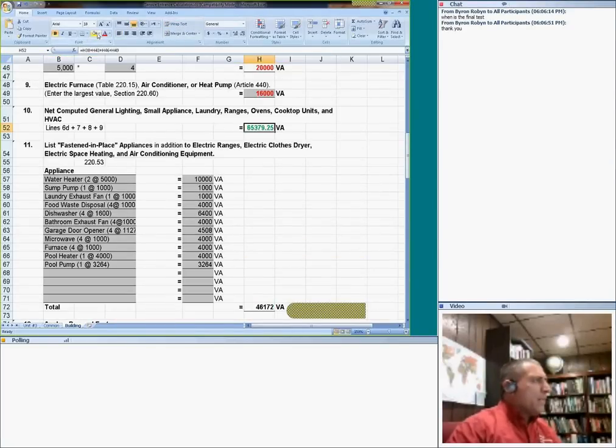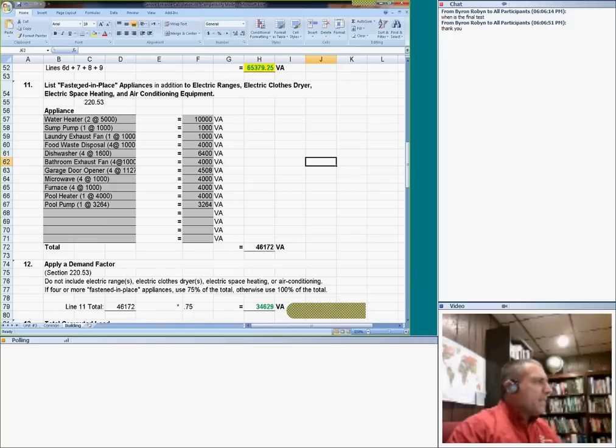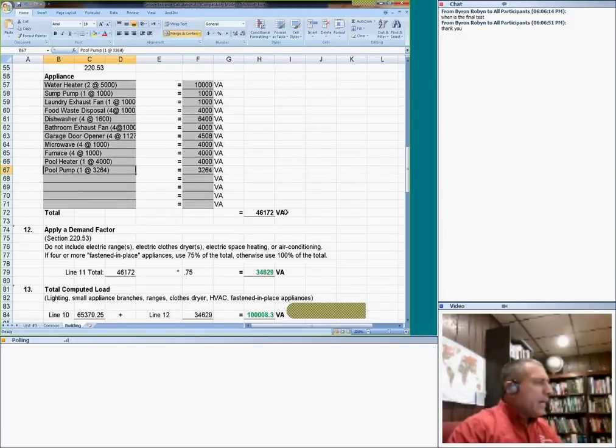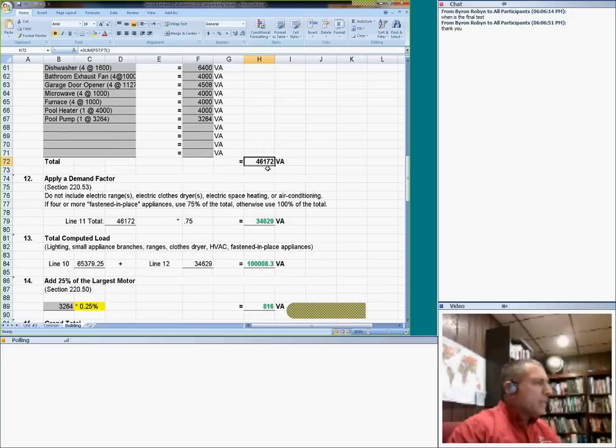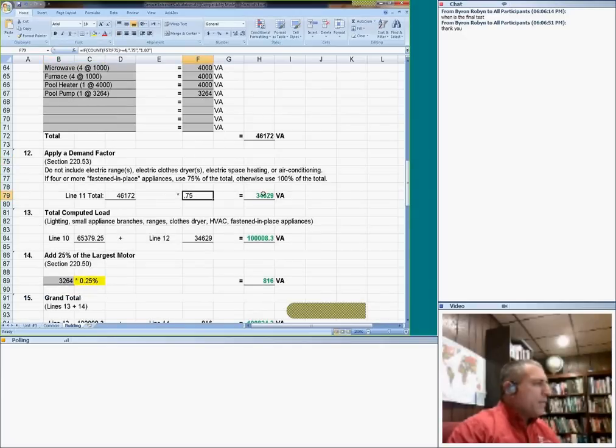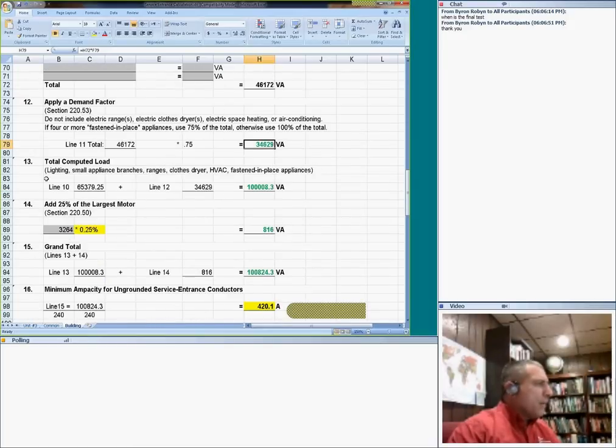So total, after you add everything up, then you add the fastened-in-place appliances. I have a water heater, a sump pump, laundry exhaust fan, food disposal, dishwasher, bathroom, garbage disposal, microwave, furnace, pool heater. I have a pool heater for this apartment, believe it or not, and a pool pump. Add them all up, and they'll get you the fixed-in-place appliances. Remember, 220.53 says if they are more than 4, cut them by 0.75. So I cut them by 0.75 because they're more than 4. As you can see, there's a bunch of them.